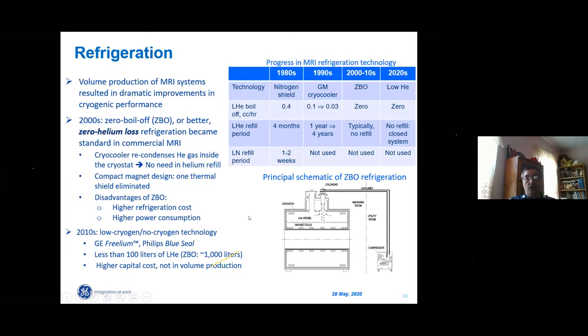In refrigeration, we see a huge advantage. We started initial magnets with a nitrogen shield. Helium boil-off was about 0.4 cubic centimeters per hour, so the refill period was once in 4 months. In addition to that, we needed to replace liquid nitrogen once in 2 weeks. First, we introduced GM cryocoolers, which dramatically reduced helium boil-off, and we got rid of the nitrogen shield, replaced by an electric refrigerator. Now all commercial MRI magnets are so-called zero boil-off magnets. Again, no helium boil-off, practically no helium refill.